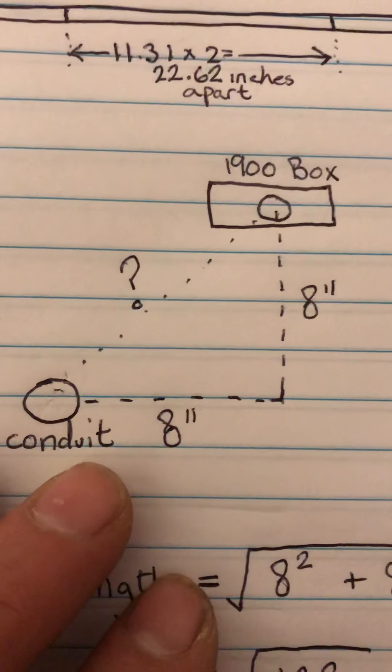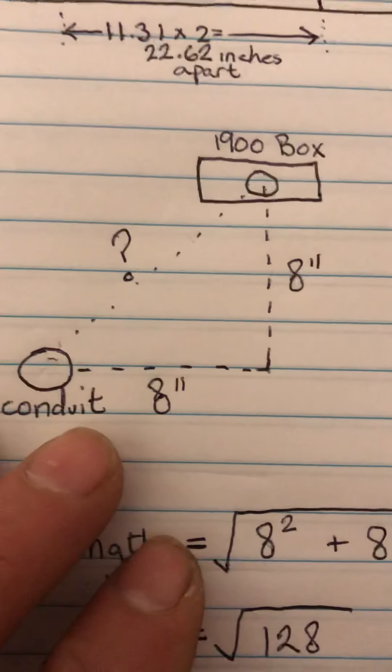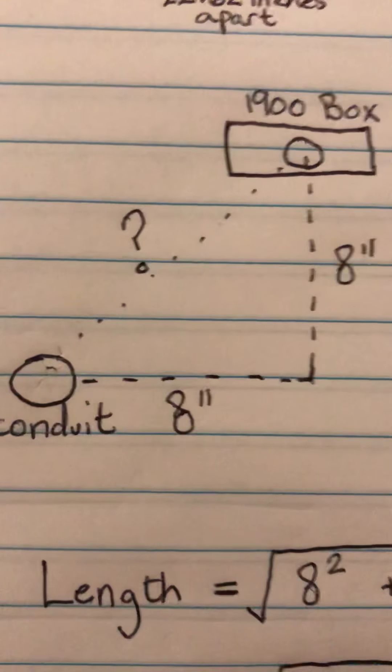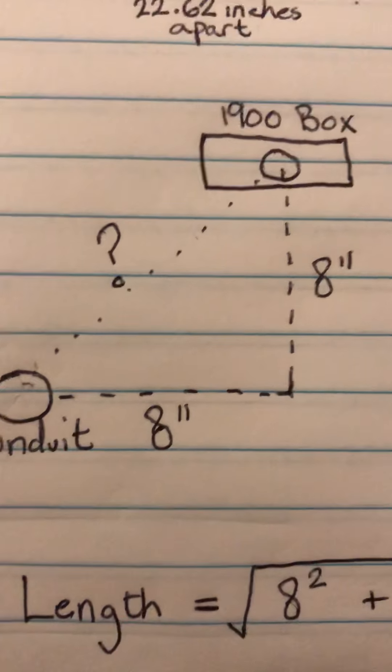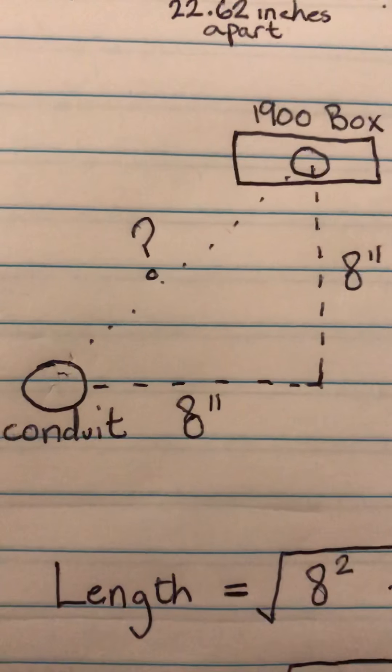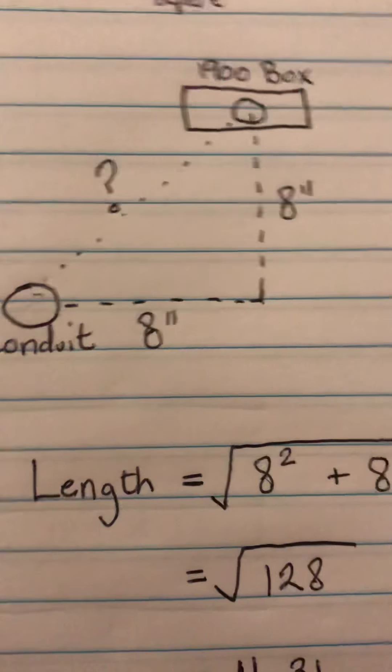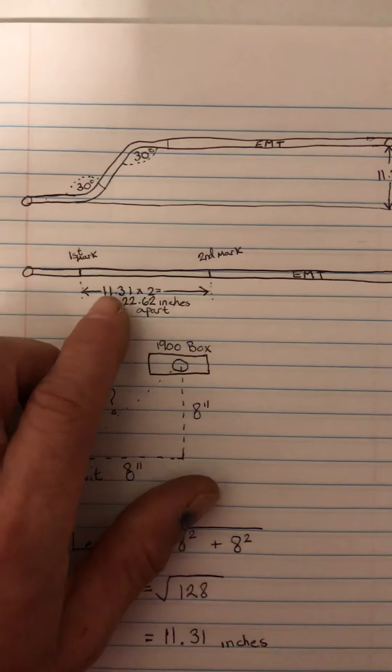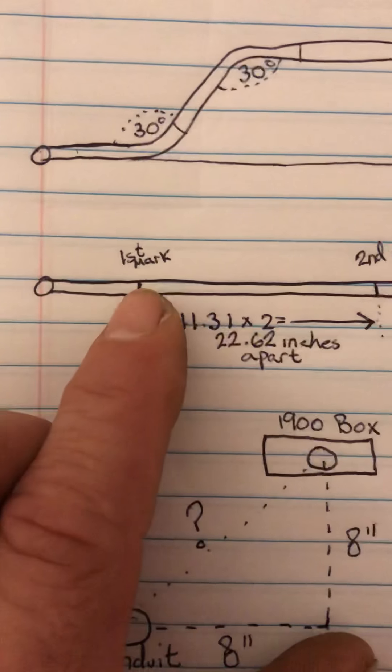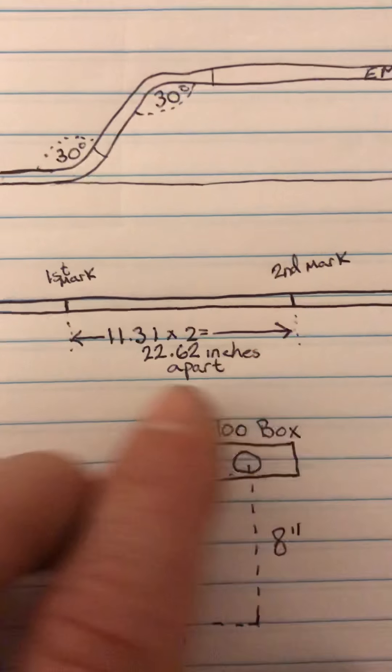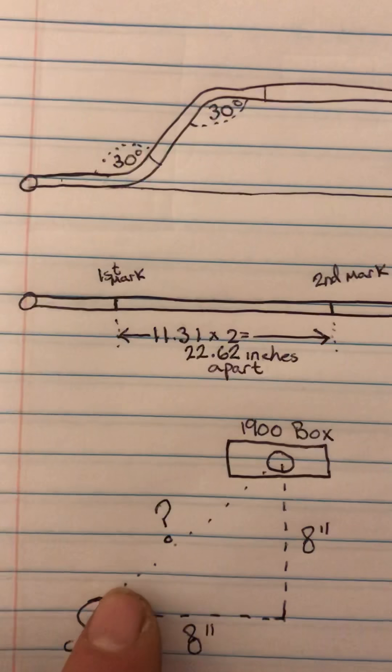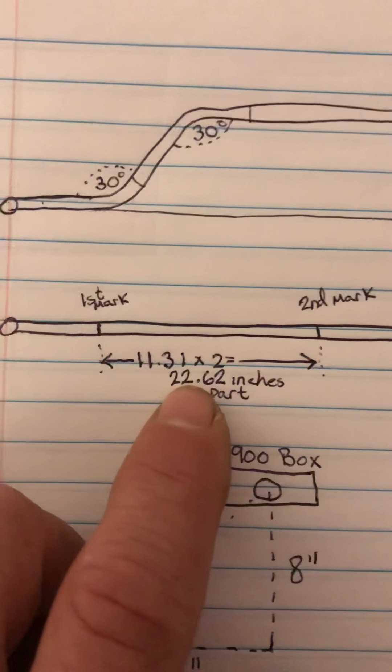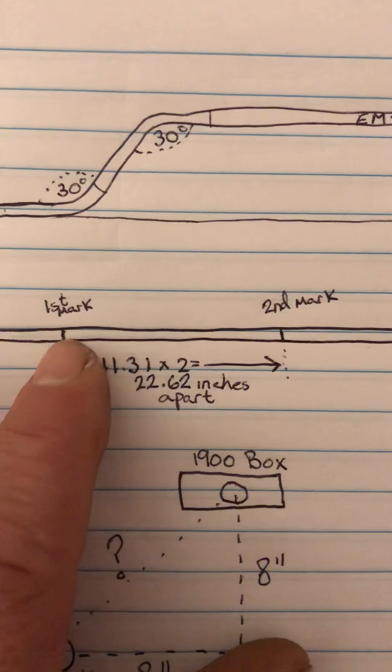Now that we've determined that, let's say we decide to go with a common angle to bend our offset on - 30 degrees. We're going to do a 30-degree offset from this conduit to this box. With a 30-degree offset, our first mark and second mark have to be multiplied by two. We take the hypotenuse, 11.31 inches, and multiply that by two, which gives us 22.62 inches apart for these marks.